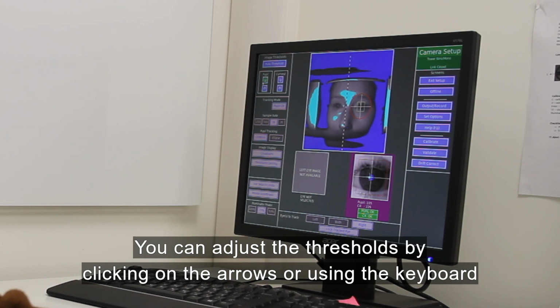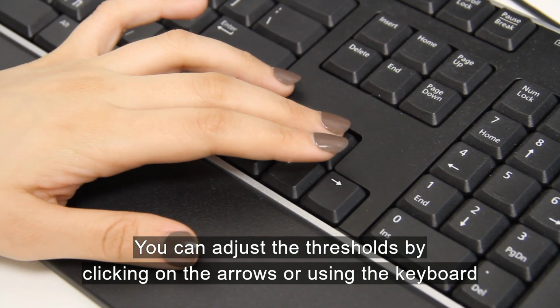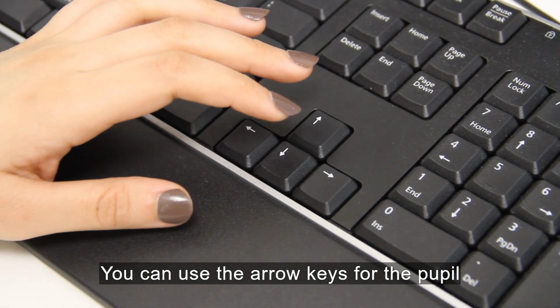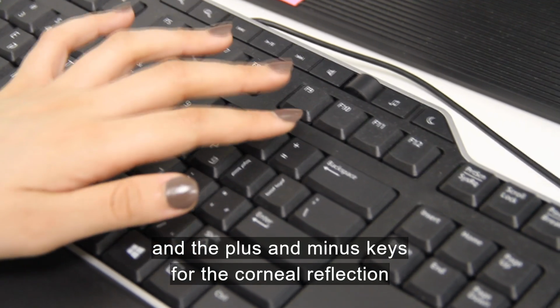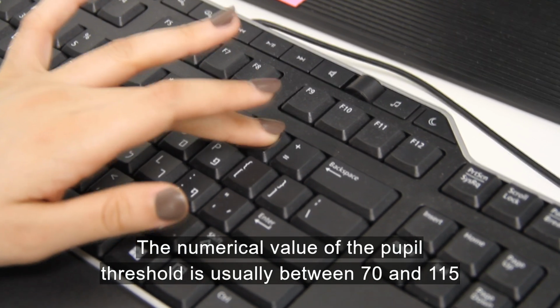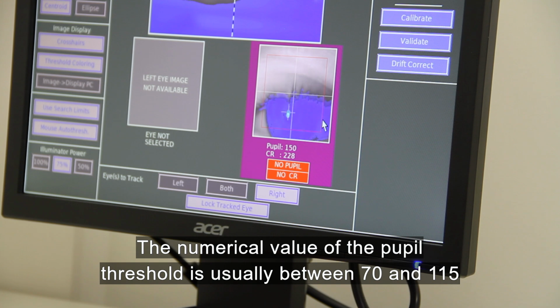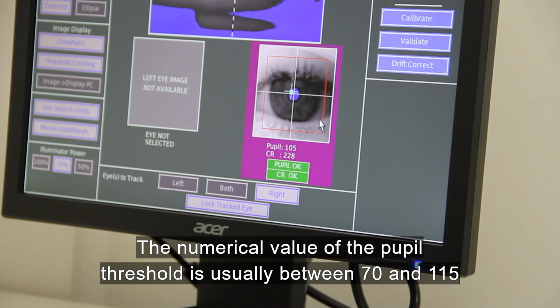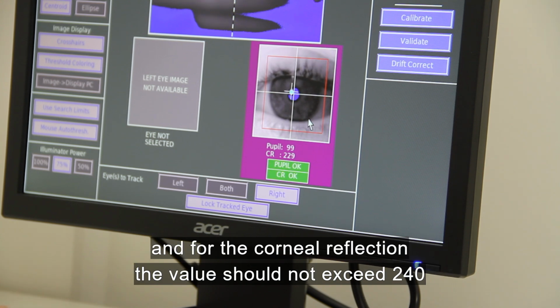You can adjust the thresholds by clicking on the arrows or using the keyboard. You can use the arrow keys for the pupil and the plus and minus keys for the corneal reflection. The numerical value of the pupil threshold is usually between 70 and 115, and for the corneal reflection, the value should not exceed 240.